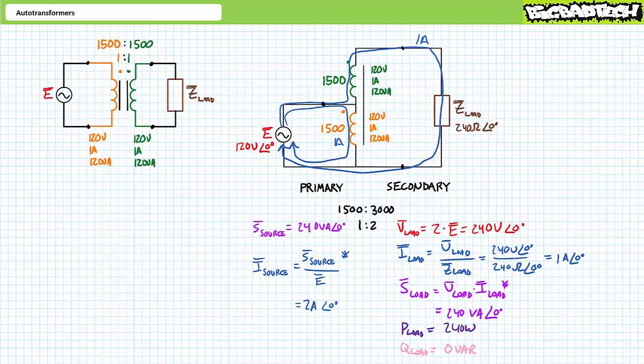As previously noted, a doubling of power rating is the maximum one might expect to achieve for autotransformers. Other turns ratios result in more power transfer, but not quite double that of a traditional transformer with isolated primary and secondary windings.